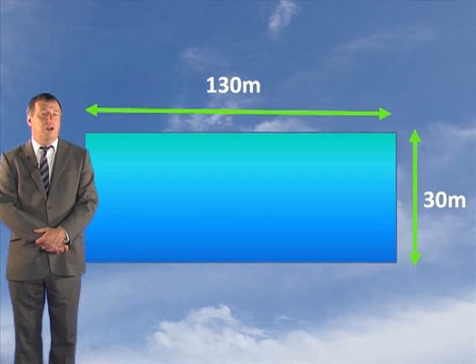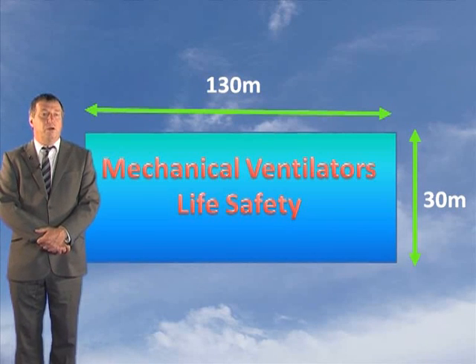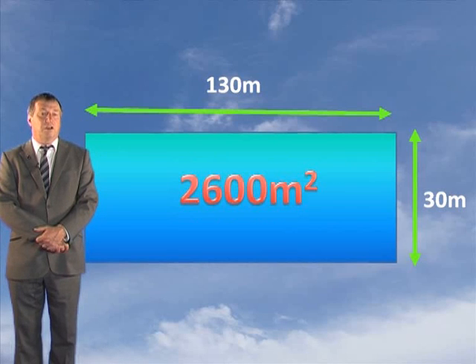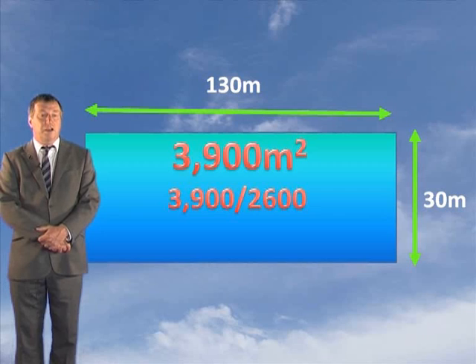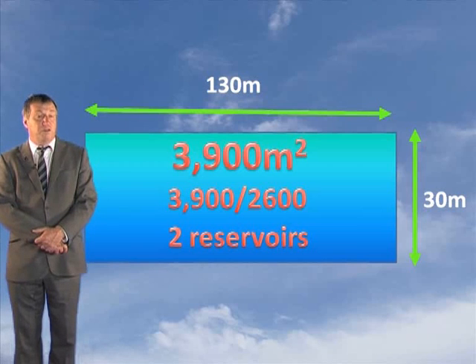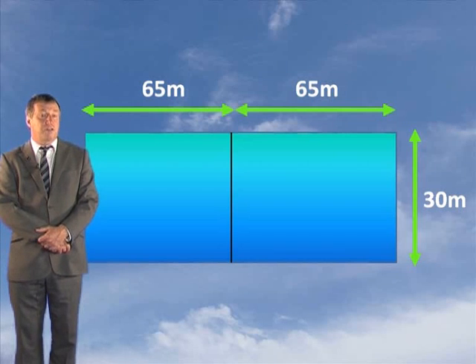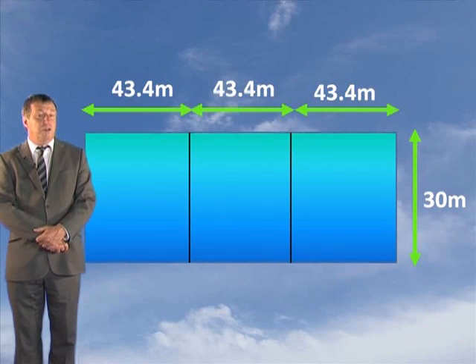Example three: determine the minimum number of reservoirs for a large out-of-town retail shop building 130 meters by 30 meters fitted with mechanical fans for life safety purposes. The maximum size is 2,600 square meters and our building is 130 by 30, which equals 3,900 square meters. We need a minimum of two reservoirs, as two times 2,600 is 5,200 square meters, which is greater than the building area. However, the 60-meter linear dimension limit applies to mechanical extract systems as well. Since one dimension is bound to exceed 60 meters, this building will in fact need three reservoirs.